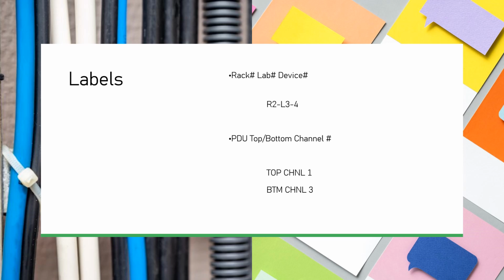They were already over capacity, so we blocked the empty plugins. On rack 1, as I'll show later, all four top devices were on the first PDU and all bottom devices were on the second—it wasn't split evenly to the eye, but due to how the amperage worked out, as Yasmin mentions later, one PDU needed to be dedicated entirely to those devices.